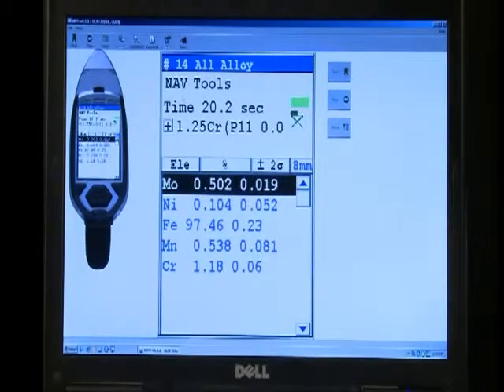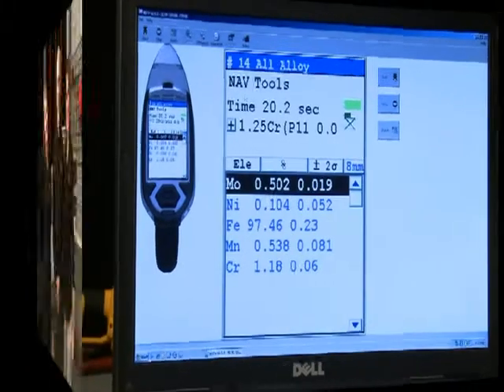This screen shows the result of the remeasurement of our check sample. As we can see from the results for each element, we are within the boundary conditions that we established previously. If your check sample reads correctly as well, you're now ready to test unknown samples. This is the end of Module 2. Module 3 will cover the measuring of unknown samples.